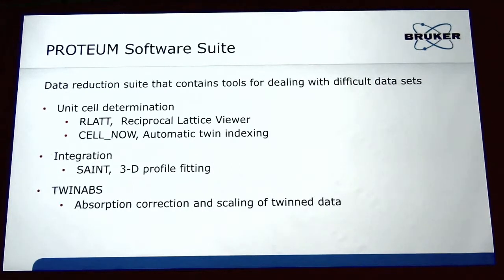We have an integration software along with the suite. So Proteum is a full data reduction suite. And SAINT is very similar in a lot of ways to XDS as far as how it approaches integration. It does a three-dimensional profile fitting, which is very useful for twin crystals, for example. And then a program written by George called TWINABS, which is for scaling, doing absorption correction and scaling twin data specifically.